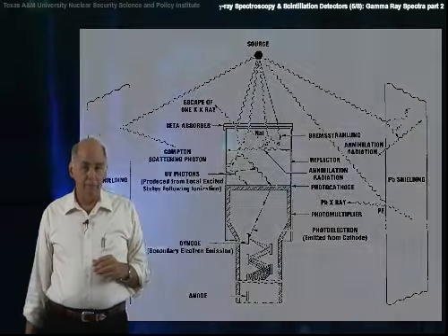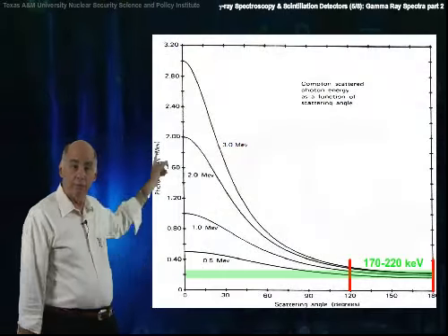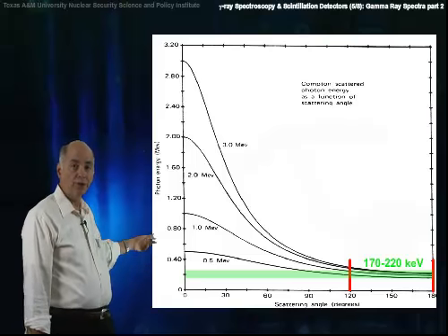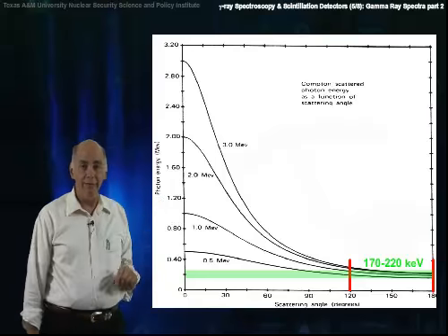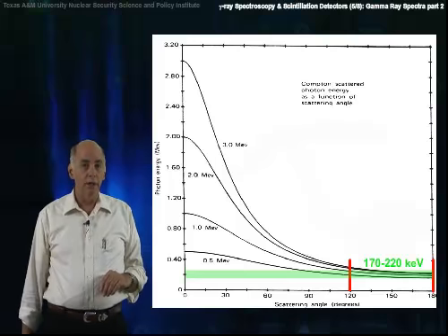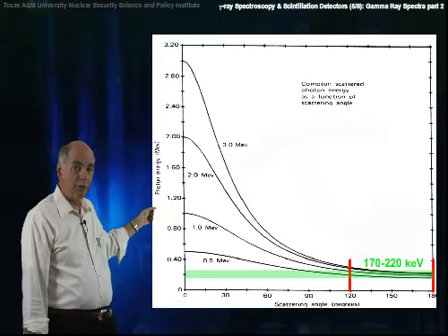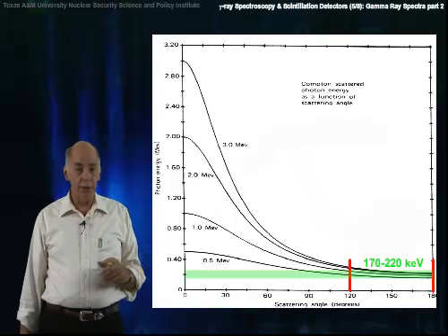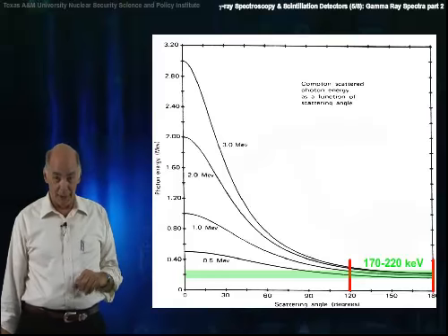Why does this happen? Because of the physics of Compton scatter, gamma rays from 5 MeV to a few hundred keV all return with energies between about 170 to 220 keV for scattering angles between 120 and 180. As you can see here, this is important for uranium-235 counting because the principal identification energy is 186 keV. I'll show you an example of backscatter peak in a minute.